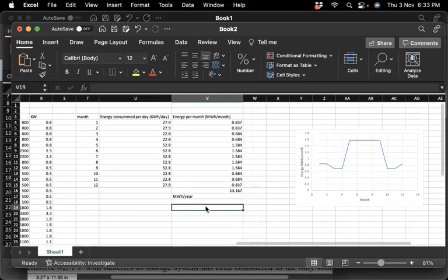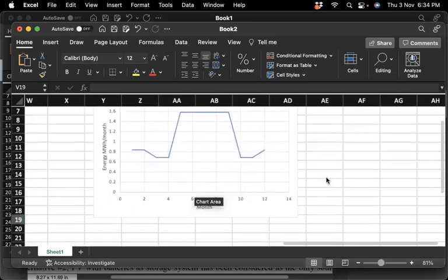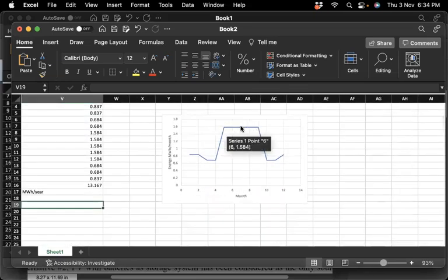So when we consider the energy or the sizing of the system, which number are we going to consider? Or in other words, are we going to size our system based on the worst case scenario that occurs in the summer, or based on the minimum power consumption that occurs in the spring and the autumn, or an average or a little bit higher than the minimum which occurs in winter, or some sort of average in between? This is actually a very challenging question to answer, because this depends on what we can call the critical level of the load.